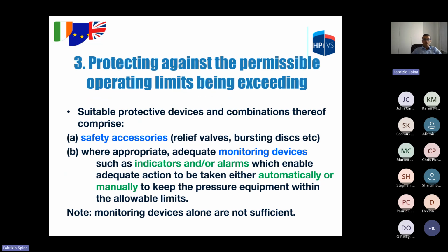The third step is protecting against the permissible operating limits being exceeded. So, suitable protective devices must be installed: safety accessories, which are always required, and where appropriate, adequate monitoring devices. Monitoring devices alone are not sufficient. Monitoring devices that enable adequate action are, for example, a pressure transmitter that activates an alarm.